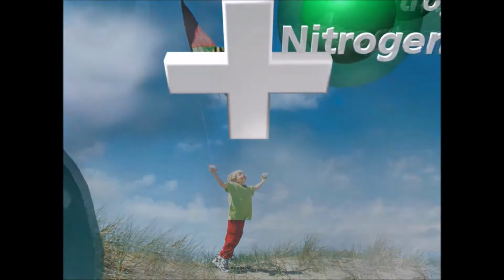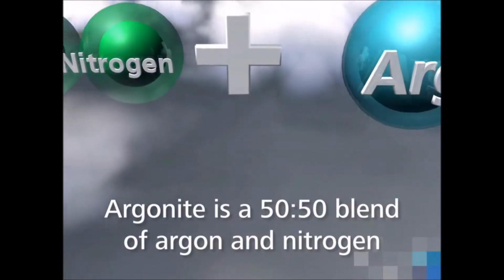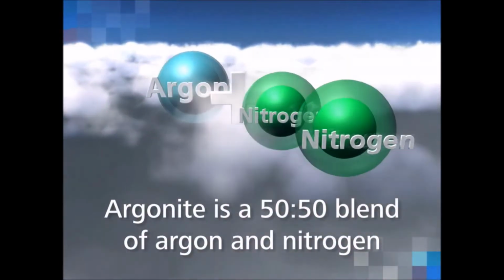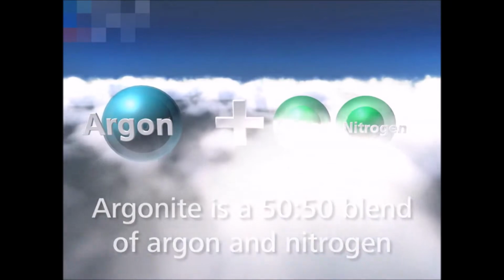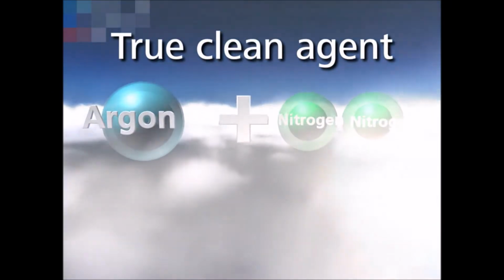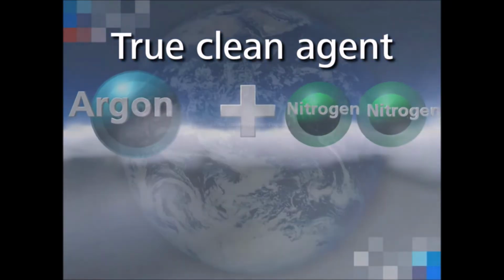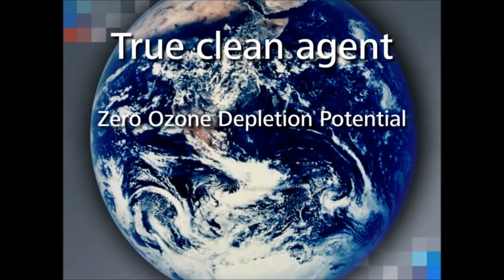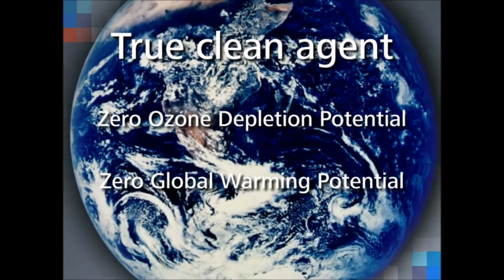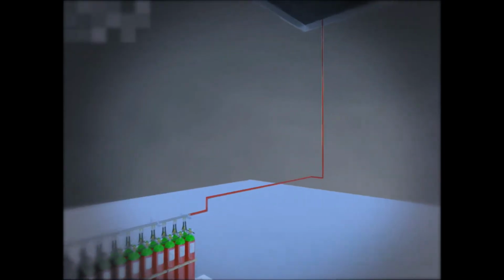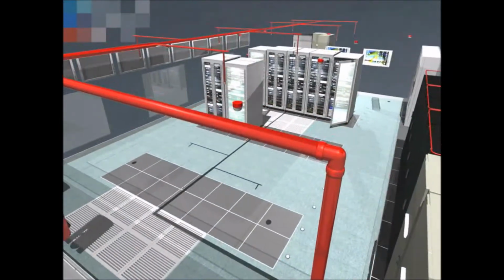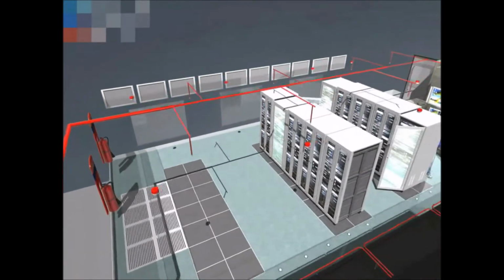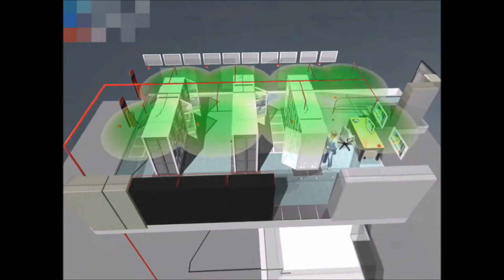Argonite is a 50-50 blend of argon and nitrogen gases, both of which occur naturally in the atmosphere. It is a truly clean agent with impeccable environmental credentials, including a zero ozone depletion potential and a zero global warming potential. It extinguishes fires in enclosed spaces. It relies on a unique controlled flow technology valve and nozzles that cover exceptionally wide areas.